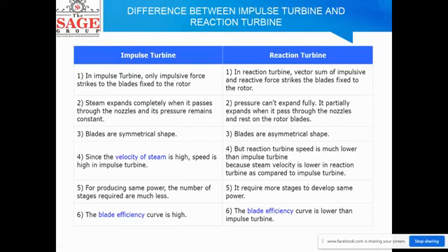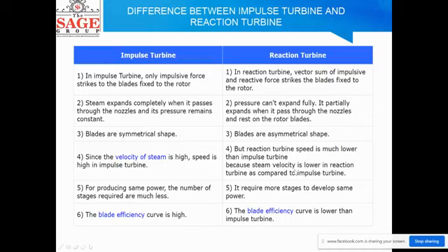Differences between impulse and reaction turbines: In an impulse turbine, only impulse force strikes the blade. In a reaction turbine, both impulse and reaction force strike the blade through the rotor, hence it is more powerful. Steam expands completely when it passes through the nozzle in an impulse turbine, whereas in a reaction turbine, pressure cannot expand fully through the nozzle alone — it also expands through the blades. Blades are symmetrical in an impulse turbine. The steam velocity is high in an impulse turbine so speed is high, but the reaction turbine runs at much lower speed. For producing the same power, fewer stages are required in an impulse turbine, while a reaction turbine requires more stages.